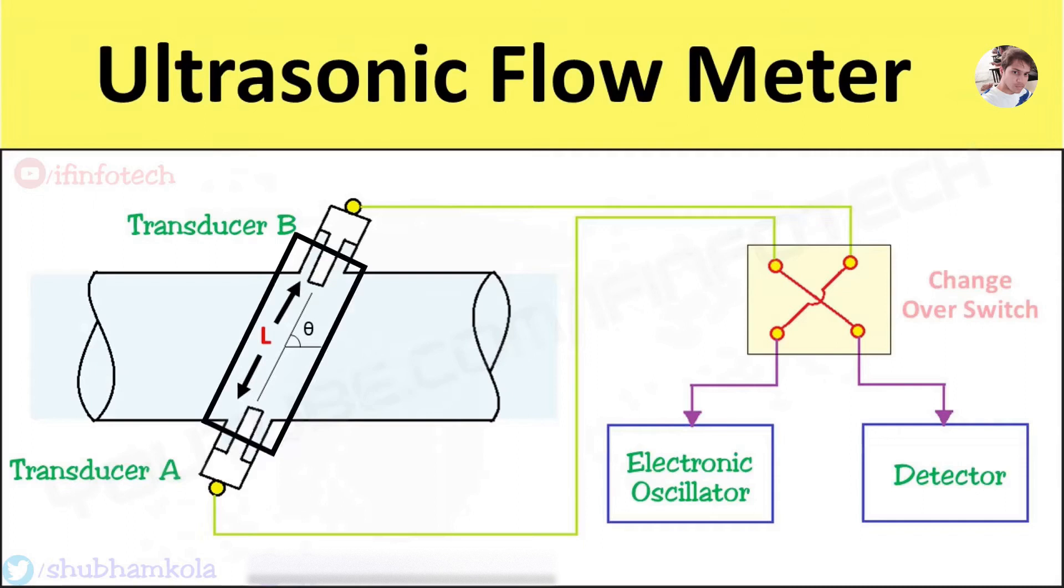Here it consists of two transducers A and B inserted in a pipeline, working as transmitter and receiver. The ultrasonic waves are transmitted from transducer A to transducer B and vice versa. An electronic oscillator is connected to supply ultrasonic waves alternatively to A and B, which work as transmitters through a changeover switch. The detector is used to measure transit time from upstream to downstream transducer and vice versa.